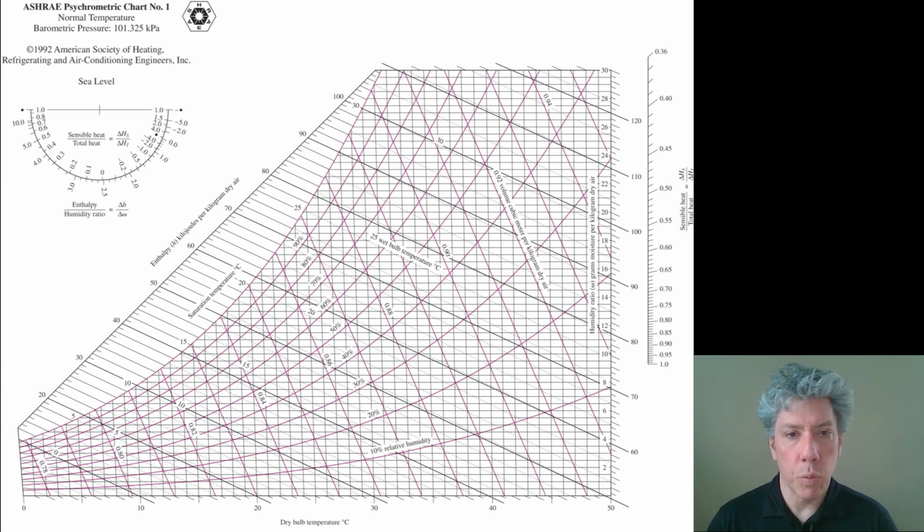You'll notice there's one that's labeled 25, wet bulb temperature in degrees Celsius. And if you go up, let's see, 1, 2, 3 black lines, you'll notice there's a dotted line very close to that black line labeled 30. It's really confusing because that 30 does not go with the dark black line. It goes with a dotted line. And it's kind of hard to remember that until you get used to it.